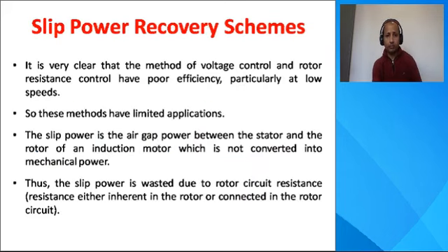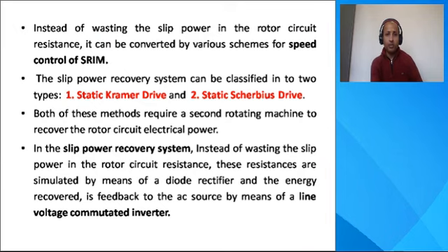Basically, when we are using a slip power recovery system, instead of wasting the slip power in the rotor circuit resistance, these resistances are basically simulated by means of a diode bridge rectifier, and the energy which is recovered with the help of this is fed back to the AC source by means of a line voltage commutated inverter.